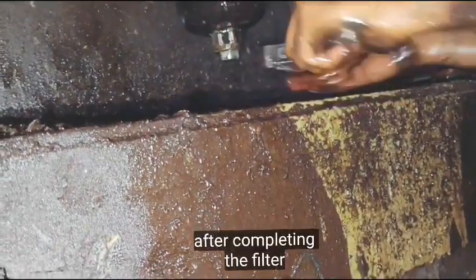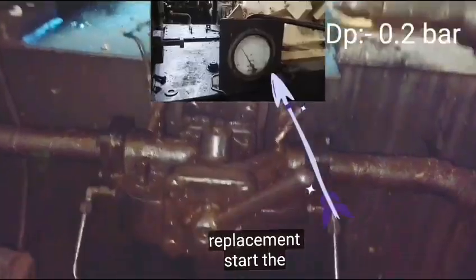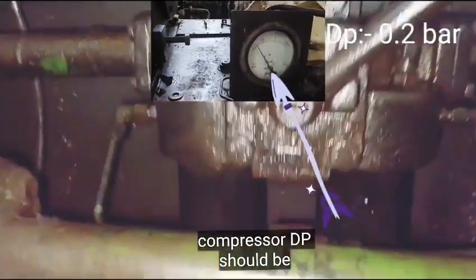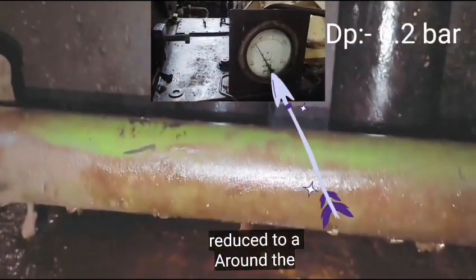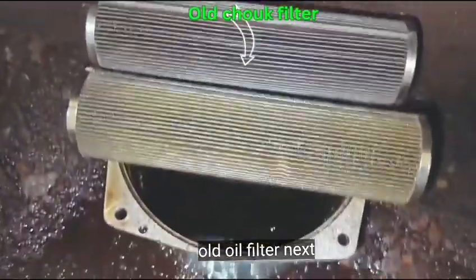After completing the filter replacement, start the compressor. DP should be reduced to around 0.2 bar after removing the old oil filter.